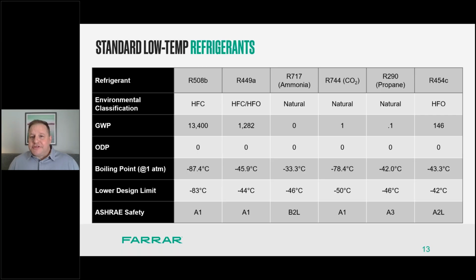Not all refrigerants are applicable for everything we need due to some of the conditions and issues. When we talk about halocarbons that are in the phase-out process, there are some viable options now. California has some stricter restrictions that are going to cause that to be a little bit of an issue. There are some HFOs in process, but unfortunately not approved yet. They're working on it. Both UL and ASHRAE are in the process of validating and approving that for charge weights and safety measures.